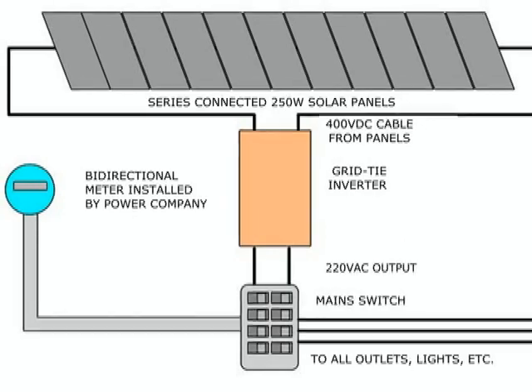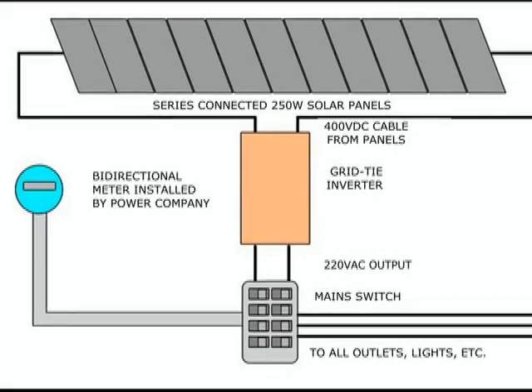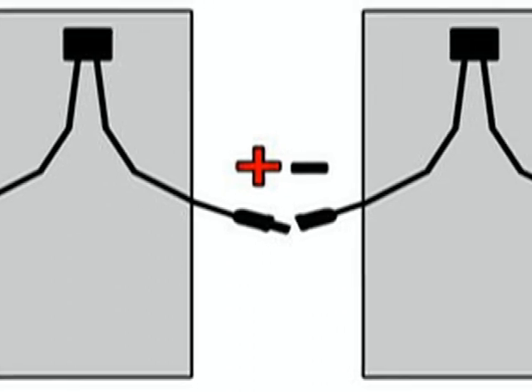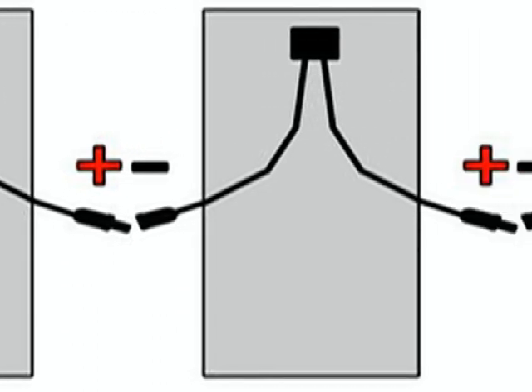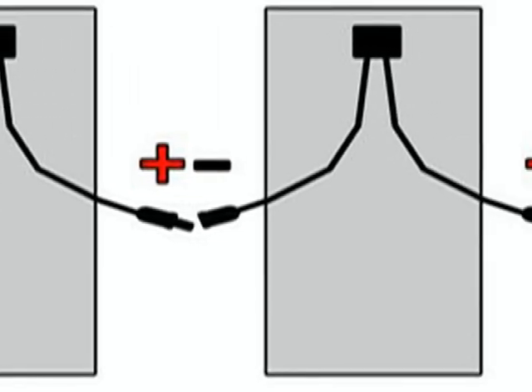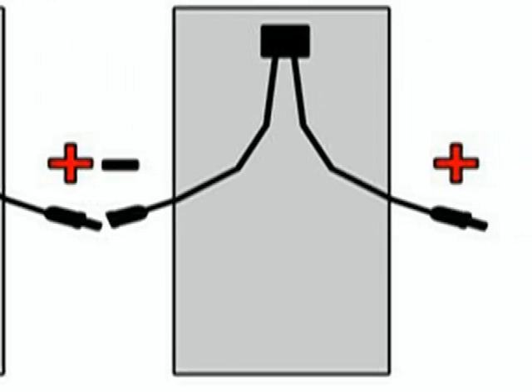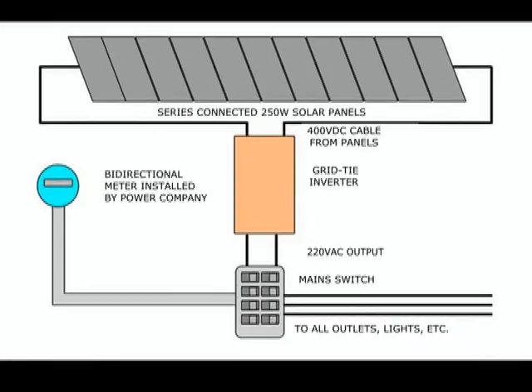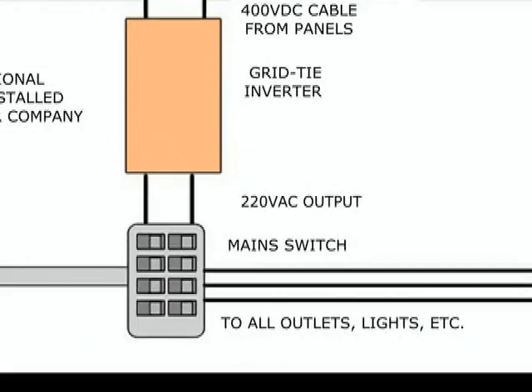It is necessary to convert DC to household AC by means of a device called an inverter, which yields AC current similar to the electricity supplied by the power company. The usual way to install a solar power plant is to wire a group of solar panels in series and send the resulting DC to a central inverter, also called a string inverter, placed indoors.